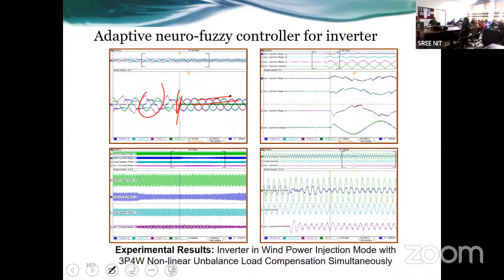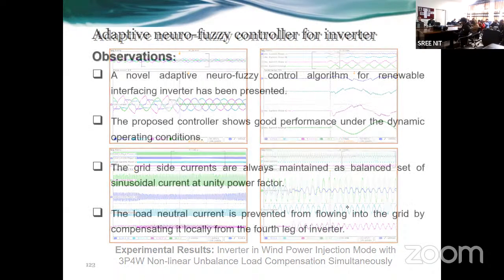Okay. So those passive devices can compensate only in steps. But here they are active devices. So that is the beauty. Actively, even within a switching cycle, you see what a smooth transition is happening. The moment I have introduced the inverter with the harmonic filtering capability, the same thing happened here. So this is phase A, phase B, phase C, and this is the neutral current. And here you have unequal currents I am giving. So this is the case.